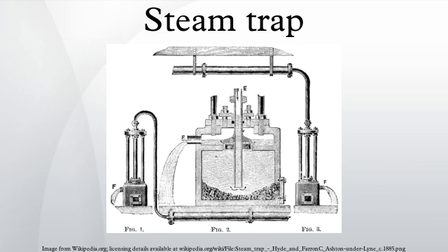It will open even if there is only steam present. This can cause premature wear. If non-condensable gas is trapped on top of the disc, it can cause the trap to be locked shut.